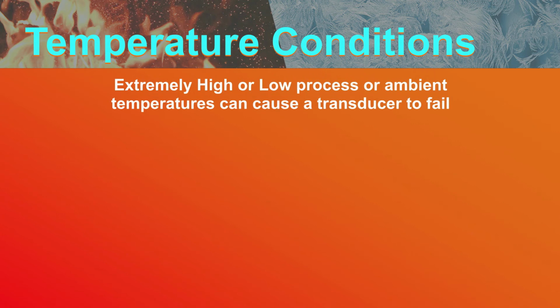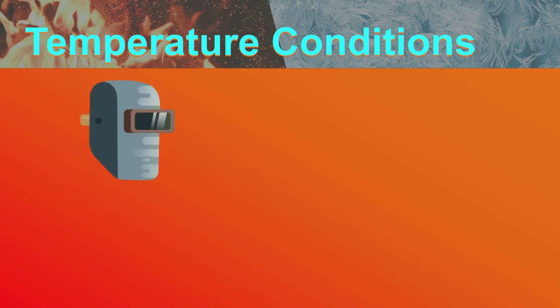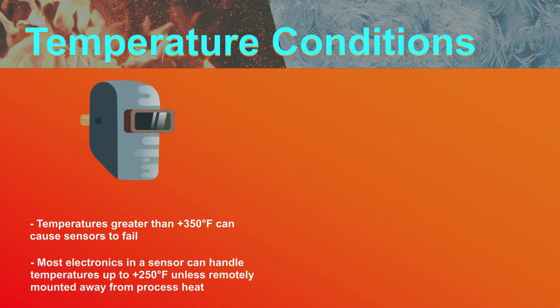Extremely high or extremely low process or ambient temperatures can cause a transducer to fail prematurely. High temperatures, typically greater than 350 degrees Fahrenheit, can cause the transducer sensor to fail. While many sensors are rated to 350 degrees Fahrenheit max, unless you remotely mount the electronics away from the process heat, they may also fail. Most electronics can handle temperatures up to plus 250 degrees Fahrenheit.